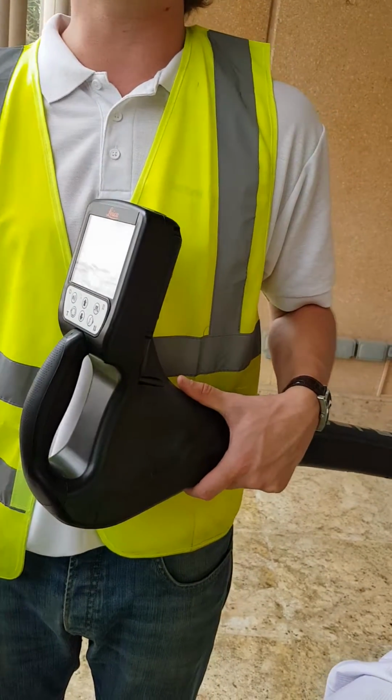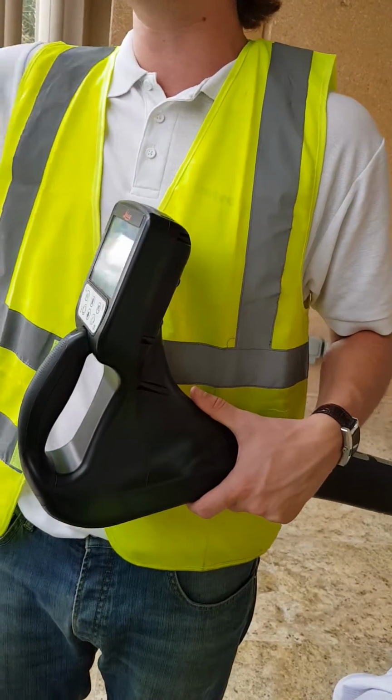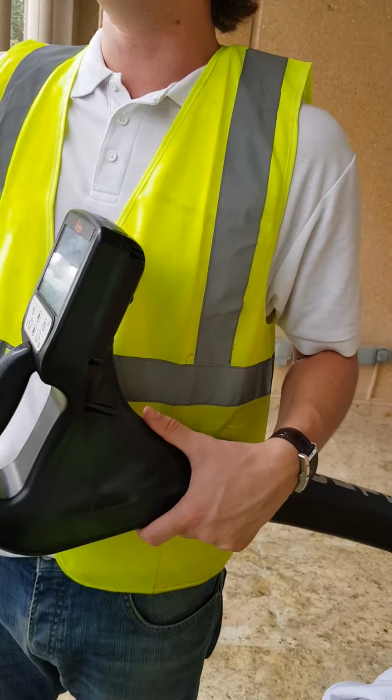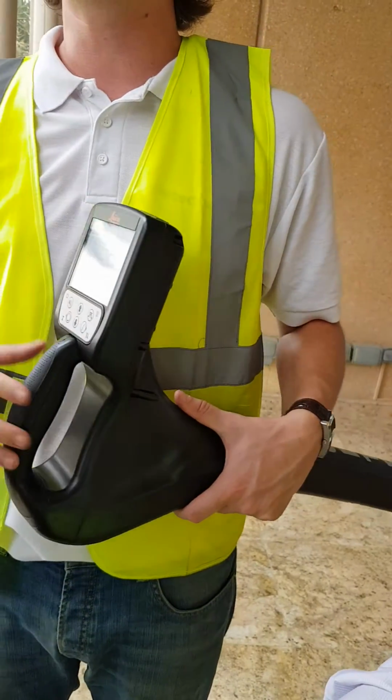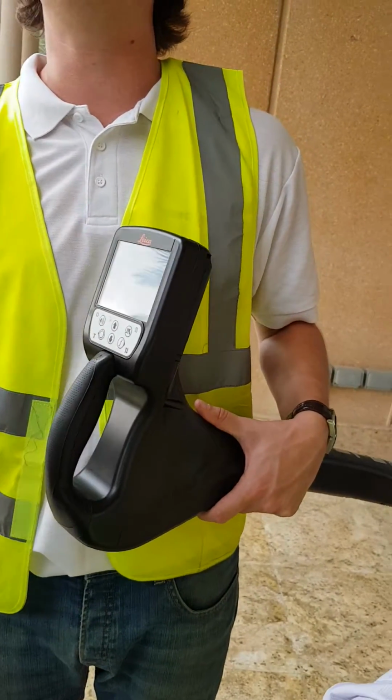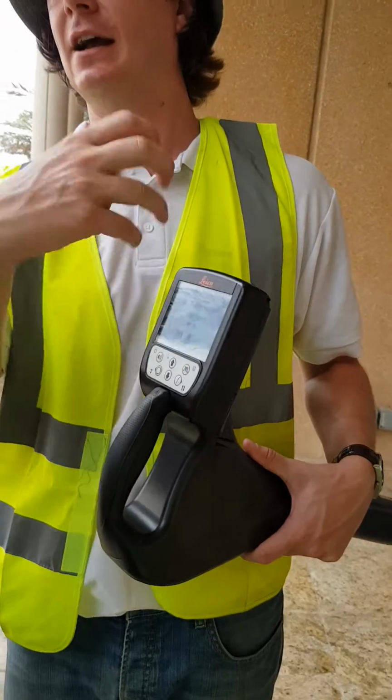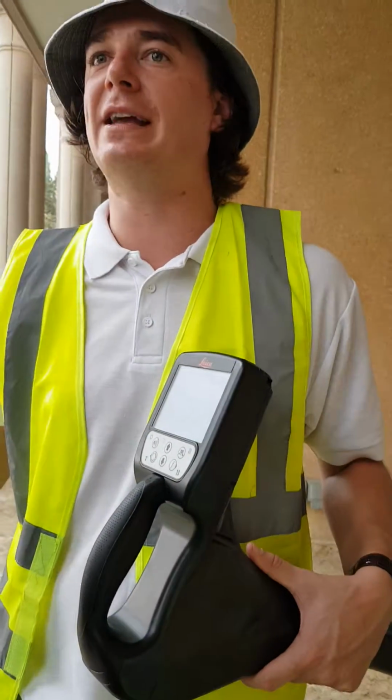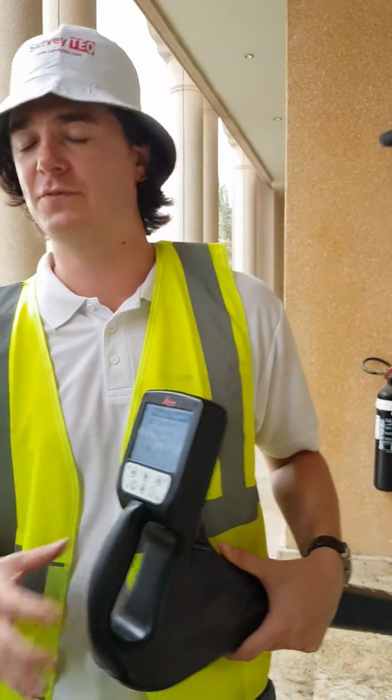This is good when we had problems yesterday where we were interfering, everybody had lots of different transmitters on and we were all using the same signal. On this one, instead of walking all the way back to the transmitter, you change the frequency here, and then the next thing on your cable you have 8 kHz coming through, or whatever frequency you choose.